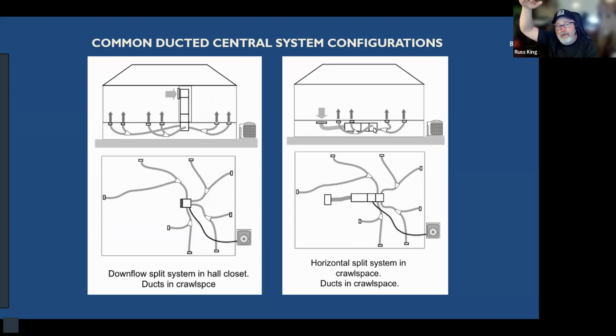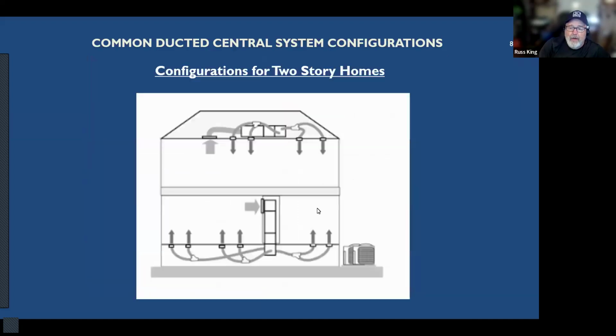If you have enough space in your crawl space, you can actually put a horizontal unit in your crawl space. So that's what this is. You'll see this more on houses built on a slope where they have 6 or 8 feet of headroom in a crawl space, and they'll hang a horizontal unit, and all the ducts will be in the crawl space. That's fairly common in some areas. And then if you have a two-story house, you may have to decide. If it's a big enough house, or if you can afford to have two systems, one serving upstairs and one serving downstairs, you can mix and match everything we've talked about up to this point.